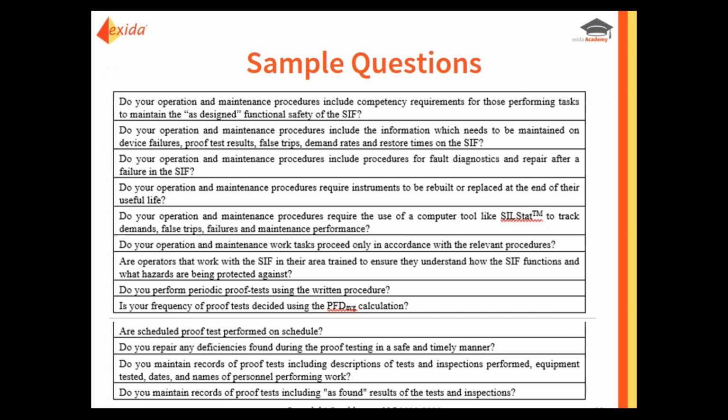Now, how you answer these questions, it's real simple. You either say always, often, never, or not applicable. And of course, as you answer these things, they're all weighted. So it's a weighted score, and the total score received determines an approximate SIL level for that site. The basis of the validity of using the questionnaire for determining SIL is that it's actually an accepted practice per the standard, per IEC 61508, using a questionnaire to determine the beta factor that describes the extent of common cause failure to be modeled when you're evaluating the safety performance of a redundant SIF architecture.